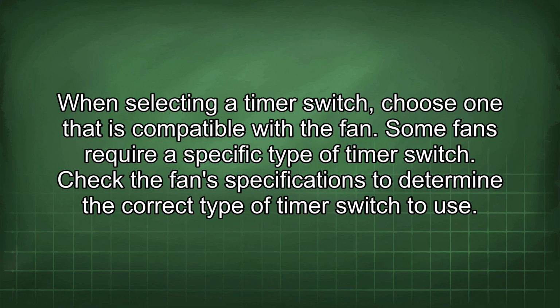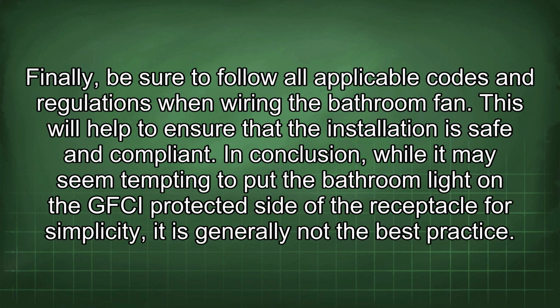When selecting a timer switch, choose one that is compatible with the fan. Some fans require a specific type of timer switch. Check the fan specifications to determine the correct type of timer switch to use. Finally, be sure to follow all applicable codes and regulations when wiring the bathroom fan. This will help to ensure that the installation is safe and compliant.